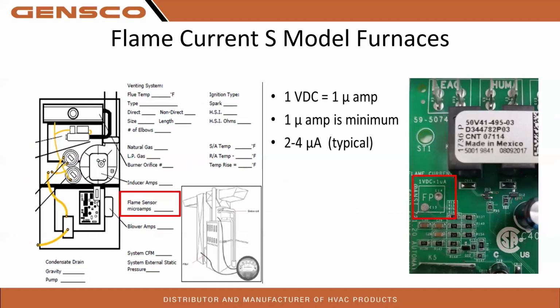Okay, on the S model furnaces, we give you nice little pads there that you can put your meter to. So you can simply get it from there with the unit running, no jumpers, nothing special. I will say that they do put a glossy epoxy across the top of that, and you may have to scratch that epoxy to get to those pads to get an accurate reading. But we're giving it to you on all of our models. Even the new S8V2 that's all linked still has this. So remember, 1 volt DC minimum, 2 to 4 typical.